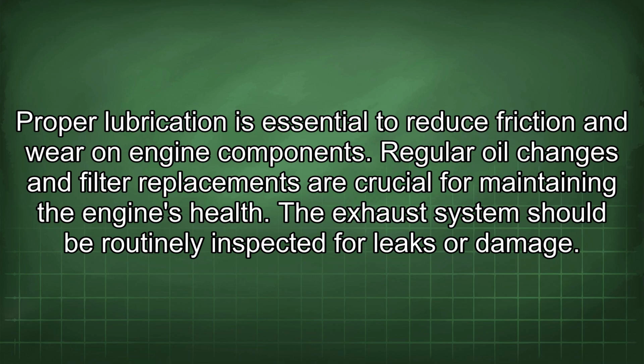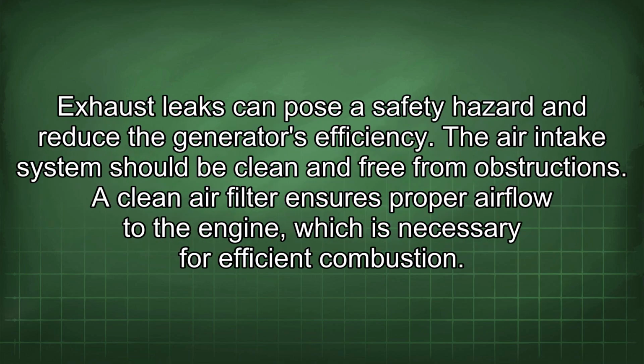The exhaust system should be routinely inspected for leaks or damage. Exhaust leaks can pose a safety hazard and reduce the generator's efficiency. The air intake system should be clean and free from obstructions. A clean air filter ensures proper airflow to the engine, which is necessary for efficient combustion.